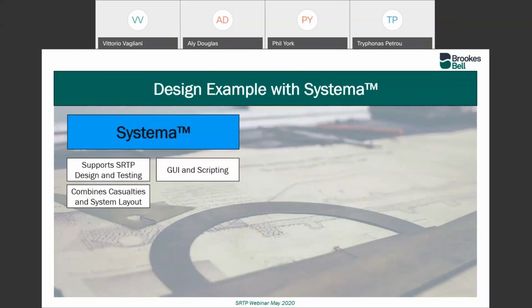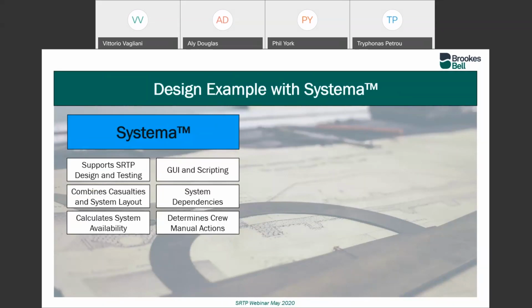Its key idea is it combines both the casualties and the system layouts, and the system dependencies can be modeled, which means that we're able to automatically determine the availability of the system following a particular casualty, but we can also automatically determine crew manual actions, so alternative configurations of the system following a casualty, which would allow us to bring that system back online. It's based around a system of automatic reporting, so the analysis that's carried out can be automatically reported, making it very easy to make changes within the model, rerun the calculations, and then automatically update the reports.